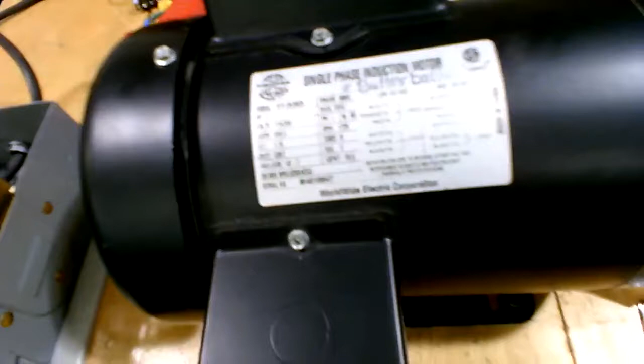To reverse the rotation of the shaft, you reverse the black and the red wires, which would be the T5 and T8, T5 and T8, which would be the red and black that are within the motor. That'll make the shaft go the other way.